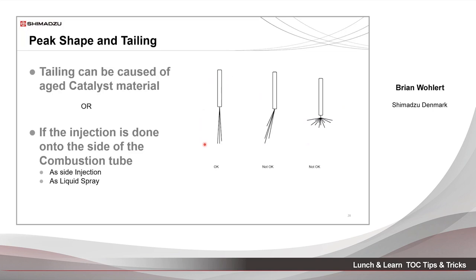When you do your startup check in the morning, you should always check that the injection is done directly on top of the catalyst material. You can see it when you open the top of the instrument.